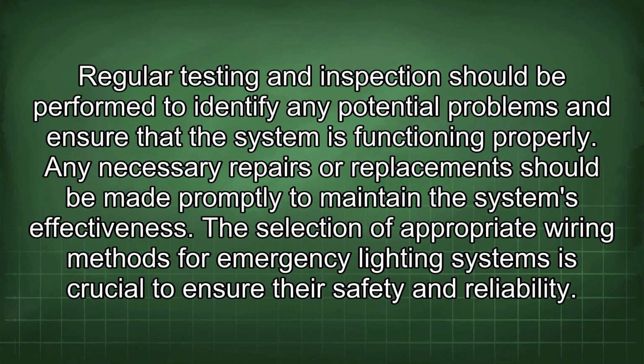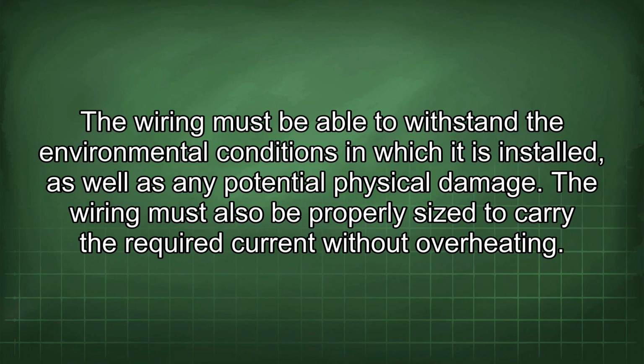Regular testing and inspection should be performed to identify any potential problems and ensure that the system is functioning properly. Any necessary repairs or replacements should be made promptly to maintain the system's effectiveness. The selection of appropriate wiring methods for emergency lighting systems is crucial to ensure their safety and reliability. The wiring must be able to withstand the environmental conditions in which it is installed, as well as any potential physical damage. The wiring must also be properly sized to carry the required current without overheating.